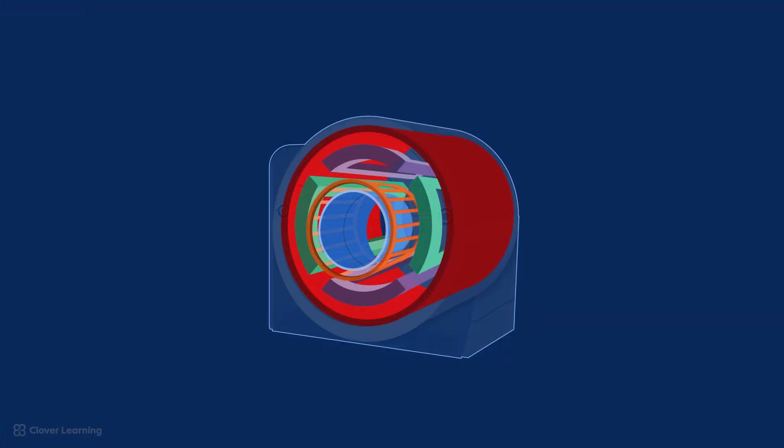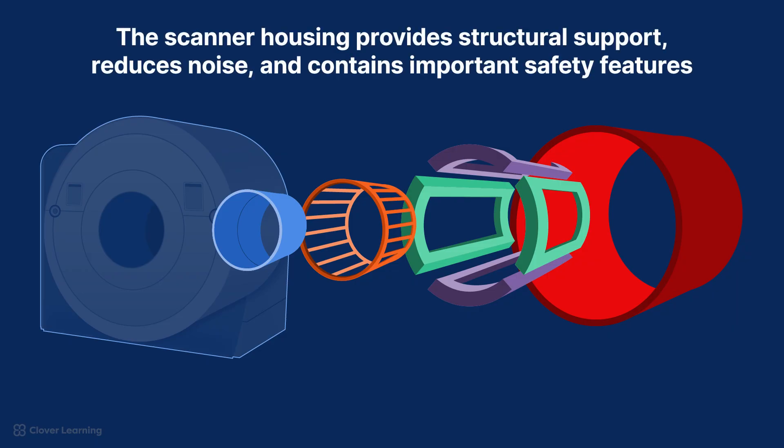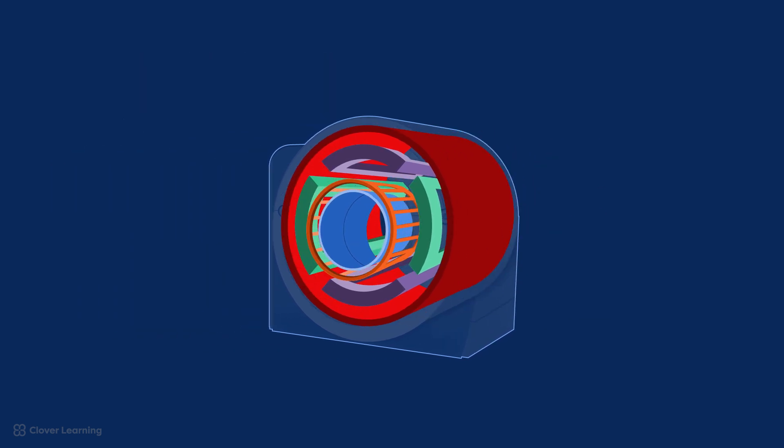The scanner housing contains the entire MRI system. It provides structural support, reduces noise during scans, and contains important safety features. The bore is the circular tunnel inside of the MRI scanner where the patient lies during an MRI scan. The bore is where the magnetic field is most uniform, or homogeneous, which is crucial for creating clear diagnostic images.